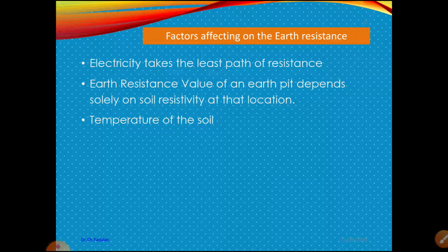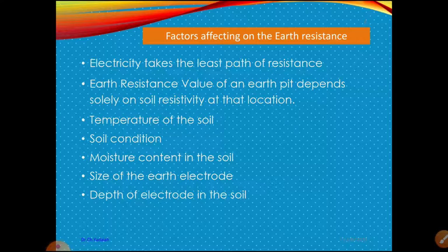Mainly, moisture is the medium through which electrons will try to flow, so our main aim is to provide proper earth at that place. The main factors are temperature of the soil, soil condition, moisture content in the soil, size of the earth electrode, depth of the electrode in the soil, and material of the electrode. Generally we use a GI pipe or copper pipe, but nowadays we are also using chemical piping, which is the latest method. Regarding the quantity of coal and salt, now we use bentonite powder, a chemical powder. These are some factors you have to remember to maintain a low resistance path on an earth pit.